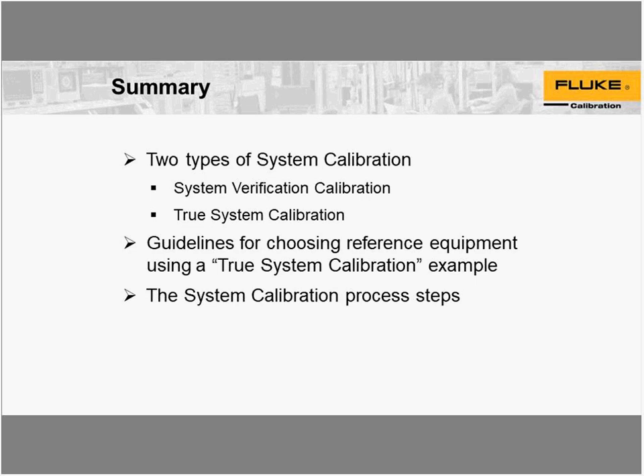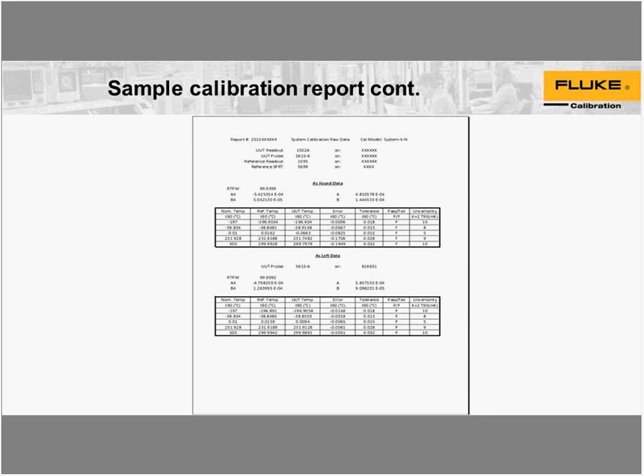Okay. This has to do with the calibration certificate that you went through at the end. Maybe you could review how you indicate the error of each coefficient and the degree of adjustment done on that calibration certificate. Okay. Basically, you're not looking at a difference in error coefficients. The coefficients are what they are. They're used to calculate the temperature that's displayed on the readout. The coefficients aren't really having an error. What you're displaying is the errors of the UUT versus the readout. Okay.